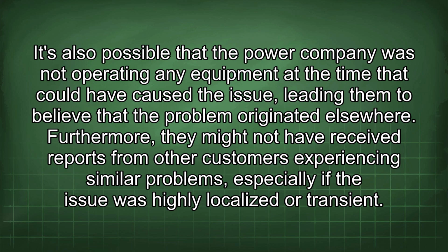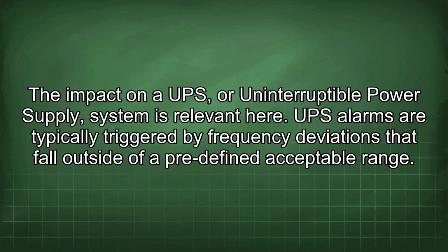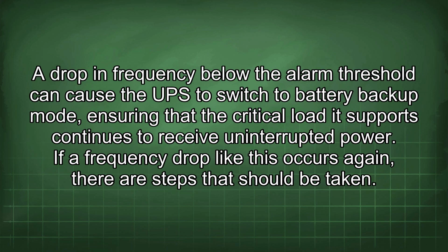The impact on a UPS or uninterruptible power supply system is relevant here. UPS alarms are typically triggered by frequency deviations that fall outside of a predefined acceptable range. A drop in frequency below the alarm threshold can cause the UPS to switch to battery backup mode, ensuring that the critical load it supports continues to receive uninterrupted power.